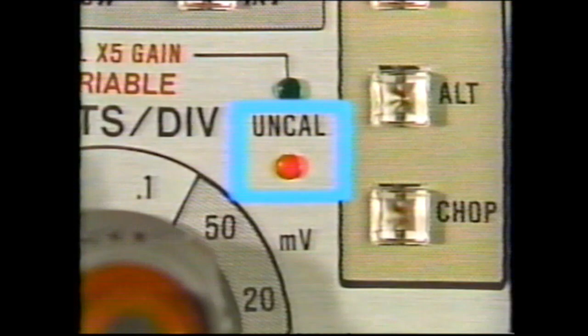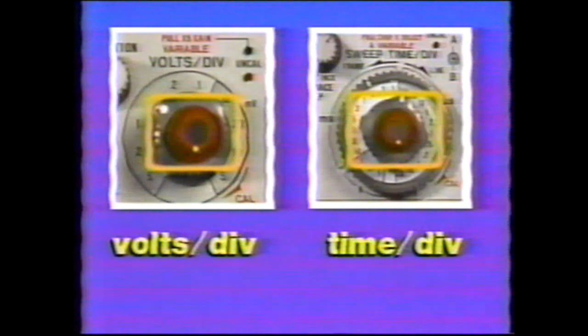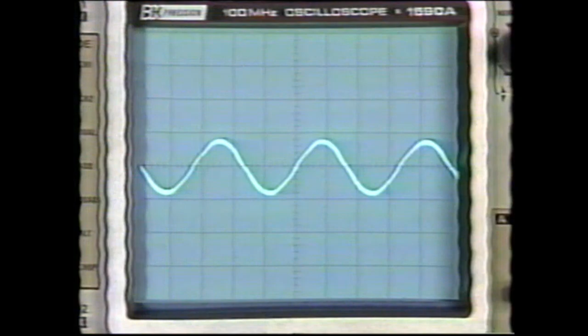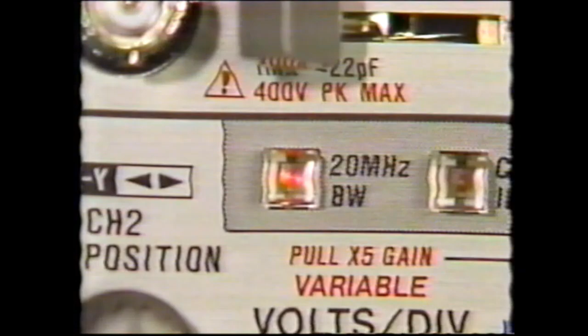The vernier controls are calibrated knobs found within other controls, such as volts per division and time per division. These controls should be in the full clockwise position if calibrated voltage measurements are desired. The ×5 gain increases the sensitivity of the oscilloscope. For instance, 5 millivolts per division sensitivity becomes 1 millivolt per division sensitivity. The 20 megahertz bandwidth button reduces the frequency response of the oscilloscope for viewing lower frequency waveforms.